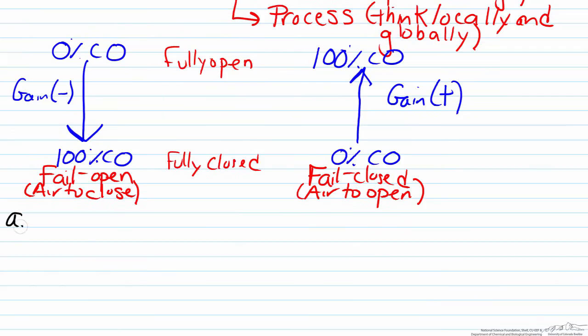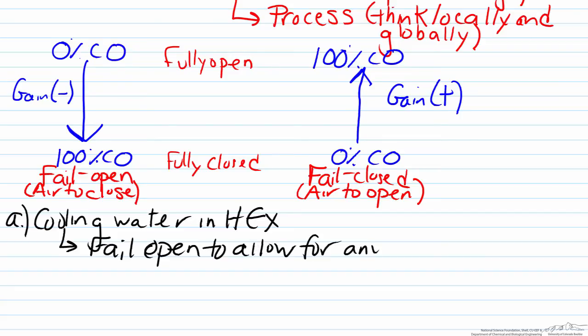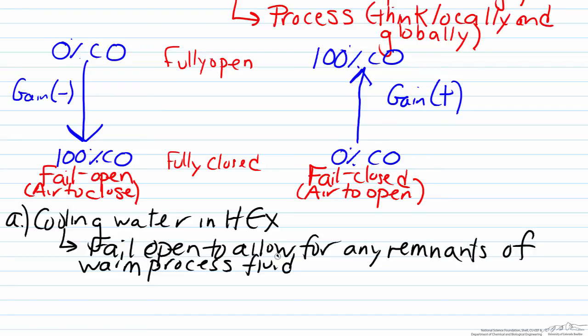Part A is the valve for cooling water in a heat exchanger. If the power were to go out, there could be hot process fluid still going through or remnants left in the heat exchanger. Therefore we would want this valve to fail open, to allow any remnants of the warm process fluid to be cooled, since allowing hot fluid to flow downstream could cause reactions or separations that are not ideal.